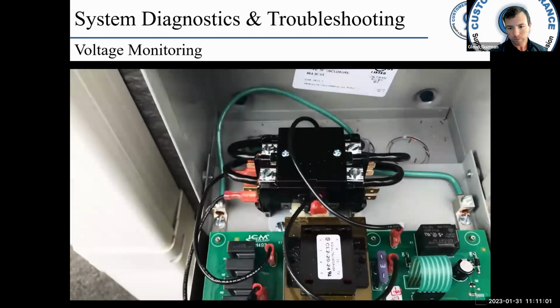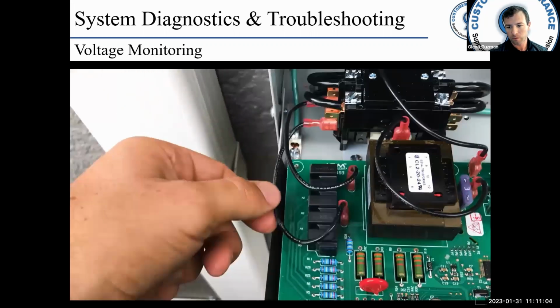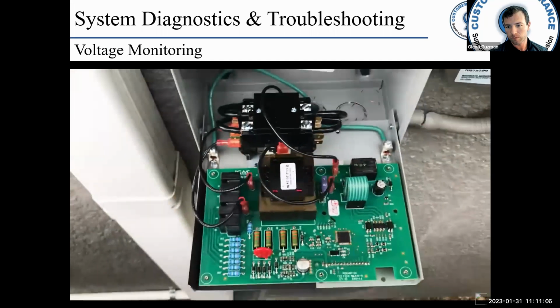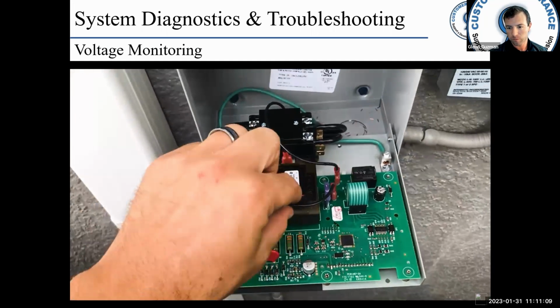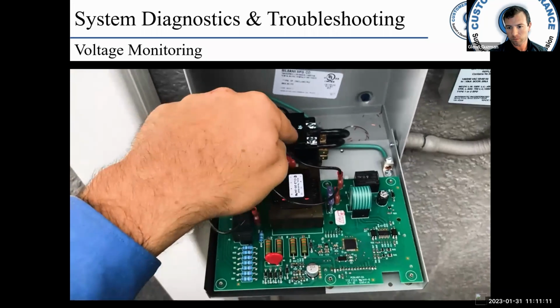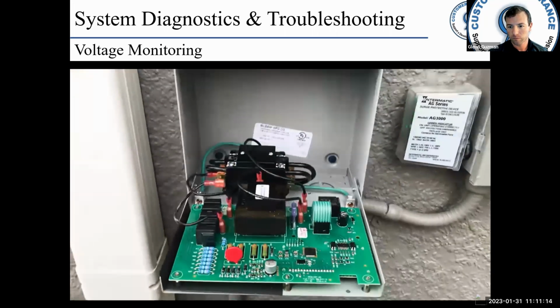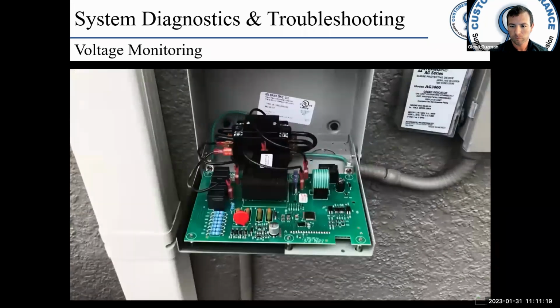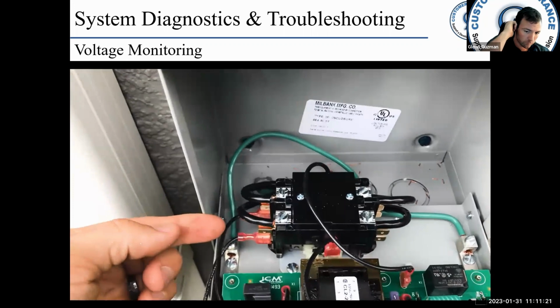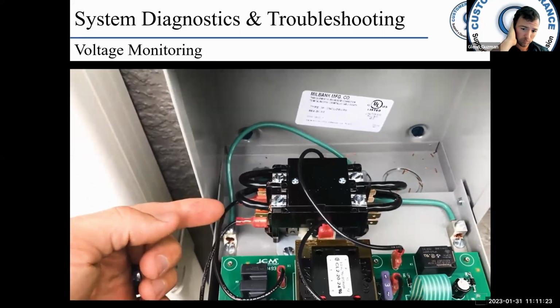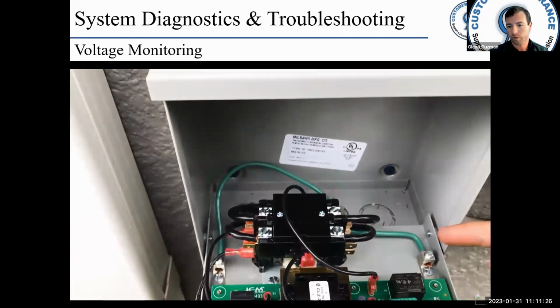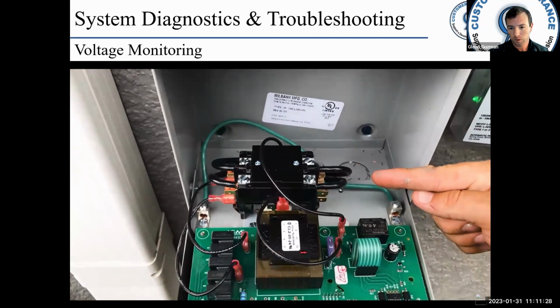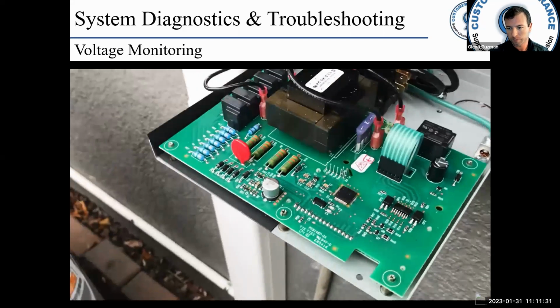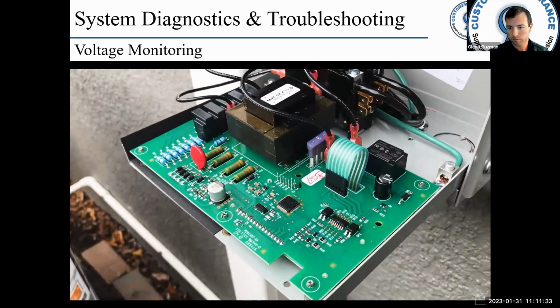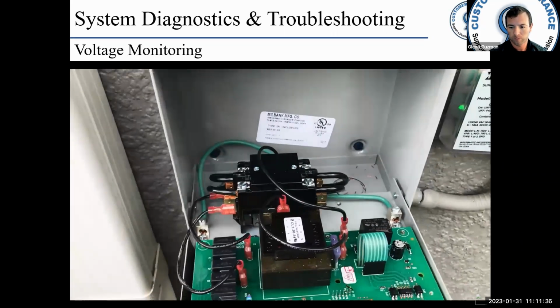So on the left-hand side, we're monitoring voltage. And then once we know our voltage is in line, then our board is going to activate our contactor, which is then going to send voltage to our actual condensing unit. Again, our line voltage is going to be wired in to the left-hand side, and then our load, which is our condenser, is going to be wired into the right-hand side. On this board, you also have a 3-amp low voltage fuse. All right, so that's pretty much how it's wired up.